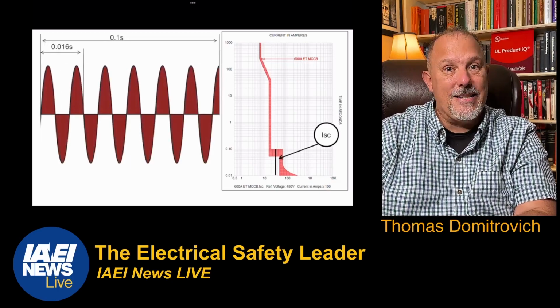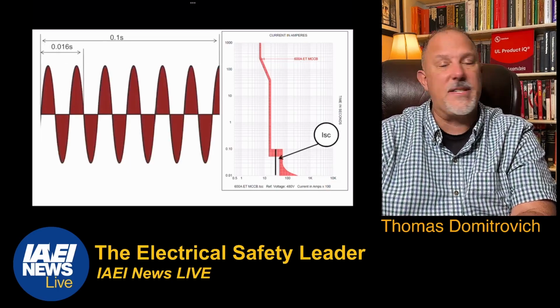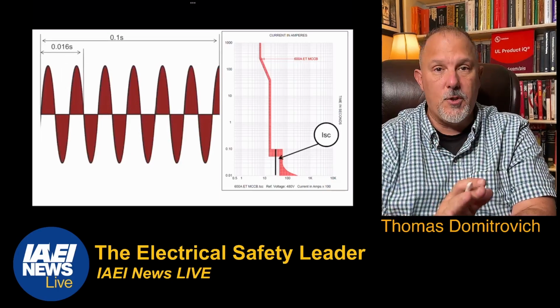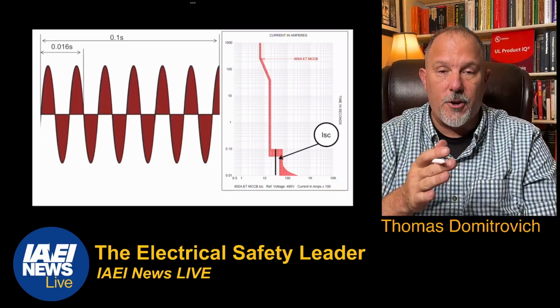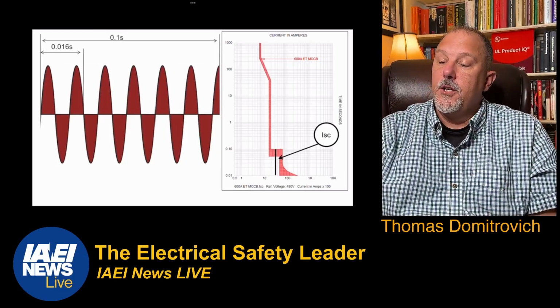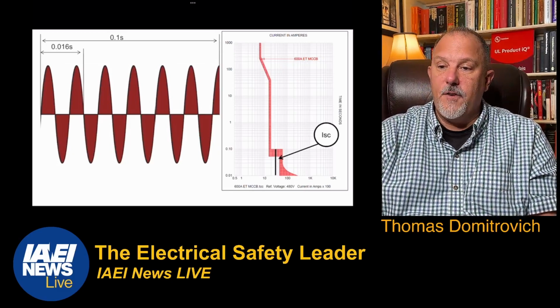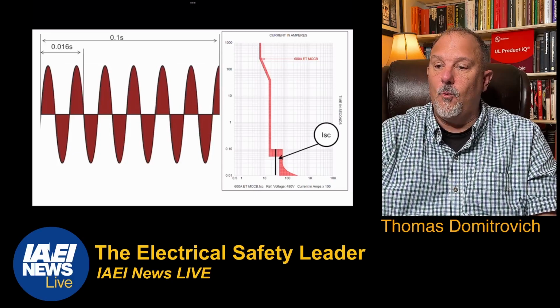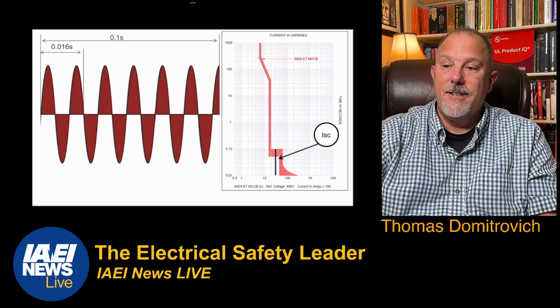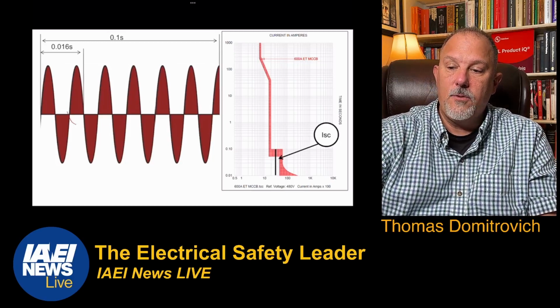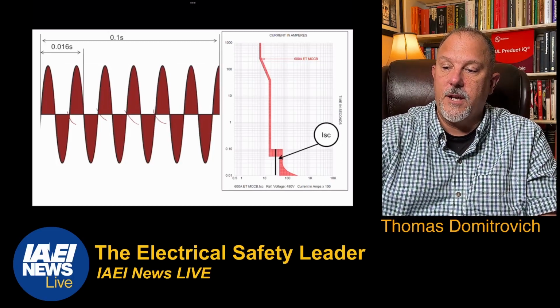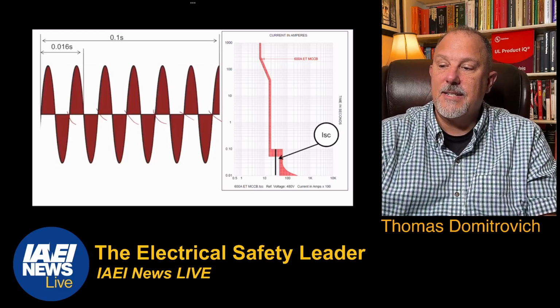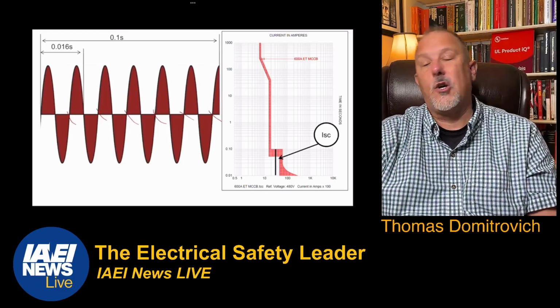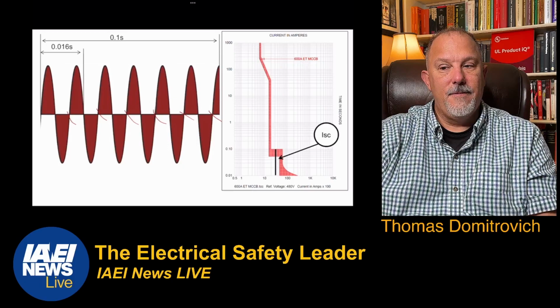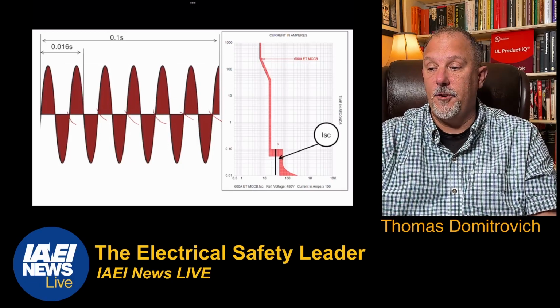If the fault current is less, this is still a 600 amp, same molded case circuit breaker. So what I'm doing here is I'm reducing the fault current on the same breaker. So I'm at a lower fault current. Now I'm at 0.1 seconds. So 0.1 seconds is 1 cycle, 2 cycles, 3 cycles, 4 cycles, 5 cycles, 6 cycles and a quarter. That's how much current I'm letting through.